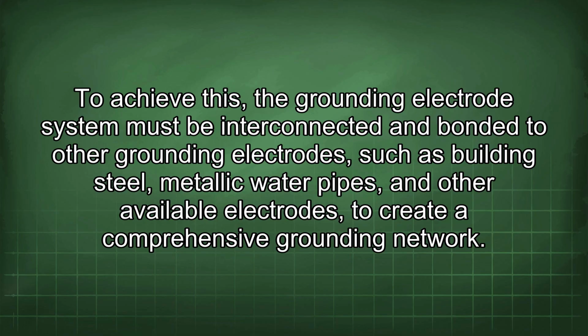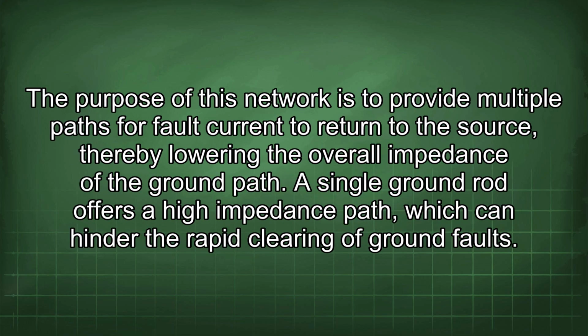To achieve this, the grounding electrode system must be interconnected and bonded to other grounding electrodes, such as building steel, metallic water pipes, and other available electrodes to create a comprehensive grounding network. The purpose of this network is to provide multiple paths for fault current to return to the source, thereby lowering the overall impedance of the ground path. A single ground rod offers a high impedance path, which can hinder the rapid clearing of ground faults.